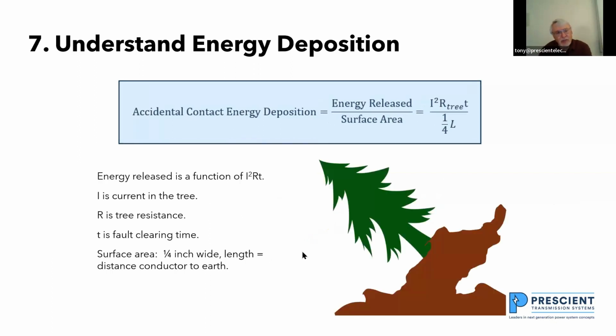Then the other thing is, what happens if you get an accidental contact? If a tree falls on the line, once again, it's energy released divided by the surface area. It tells me how many watt seconds per square inch I'm getting on the tree, and that's what I'm focused on. That's the energy in the calculation where I was looking at the vegetation ignition. Typically for something like white pine, we assume you have 2,000 ohms per foot of tree. So if a 40-foot tree falls on a transmission line, that's 40 times 2,000, which is 80,000 ohms. So the current is going to be small.